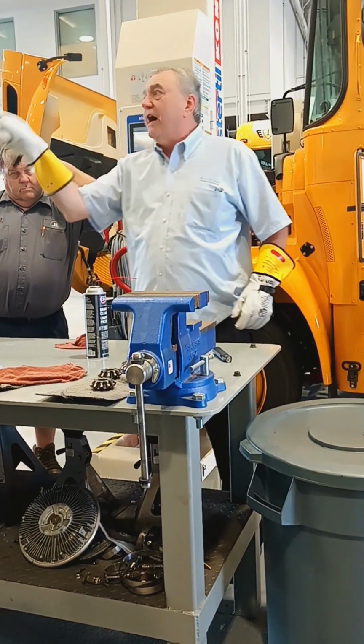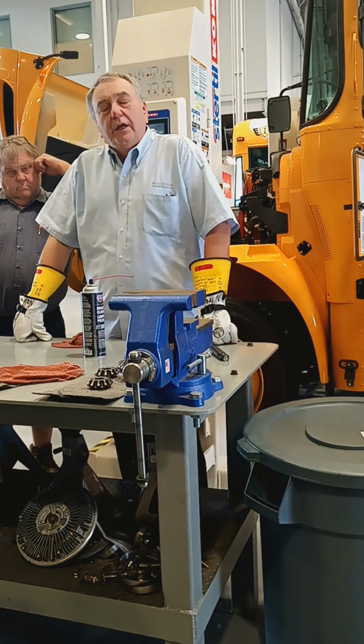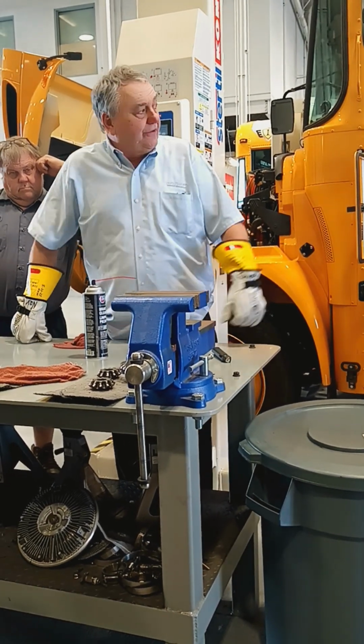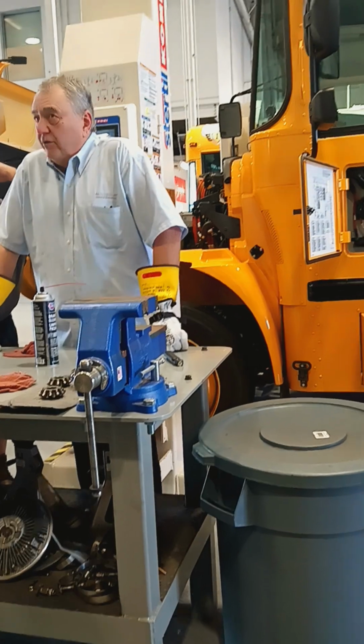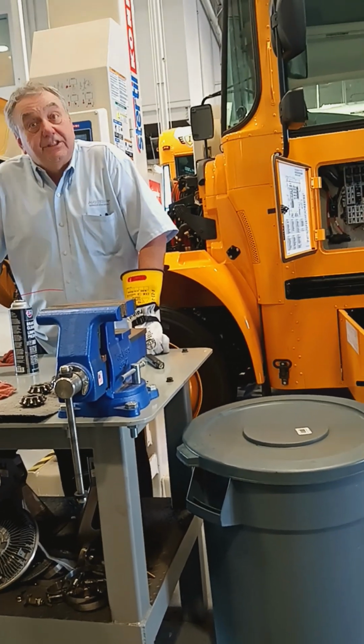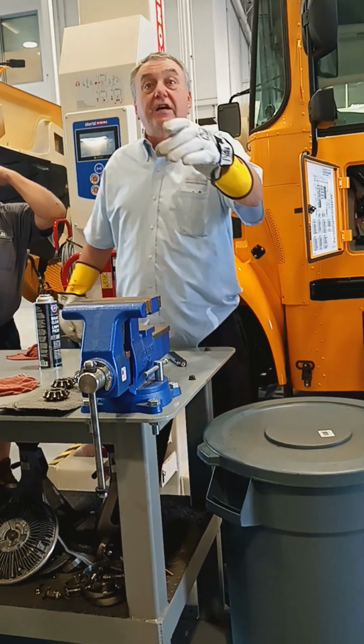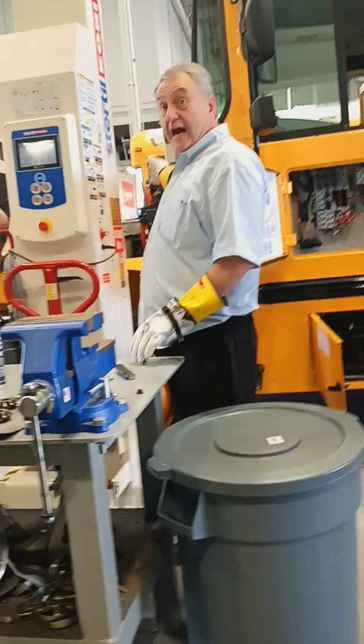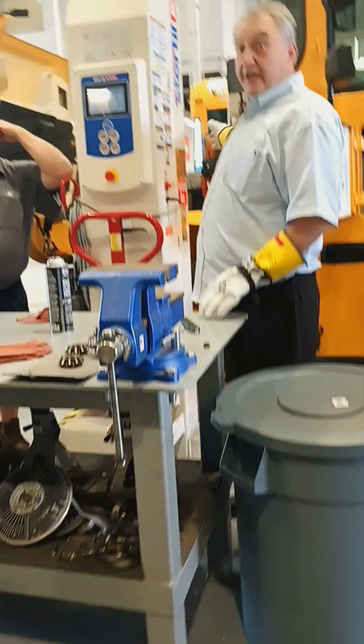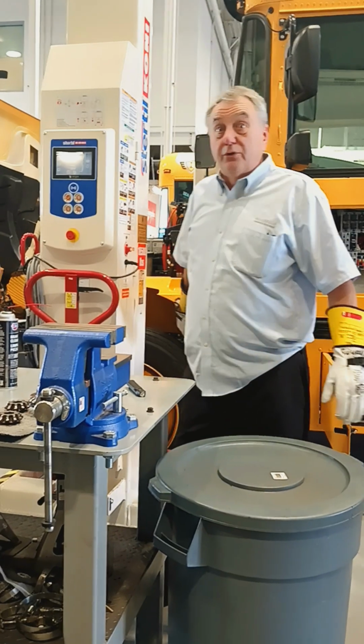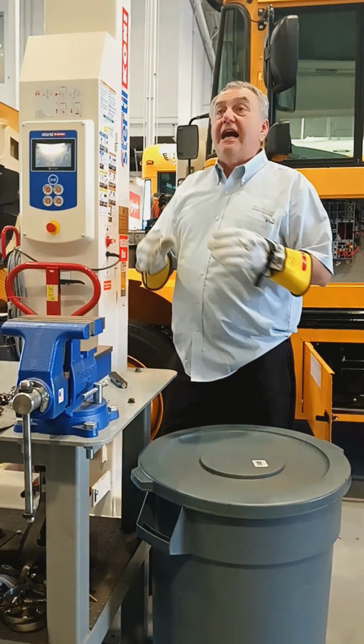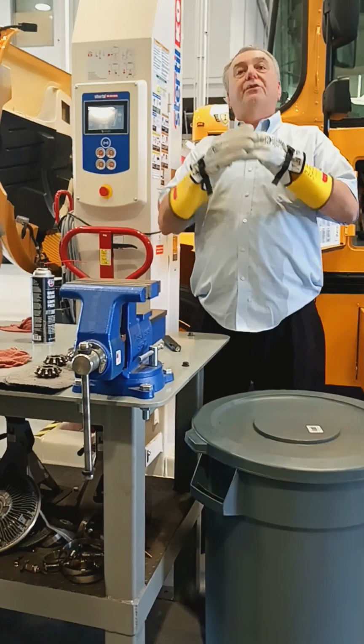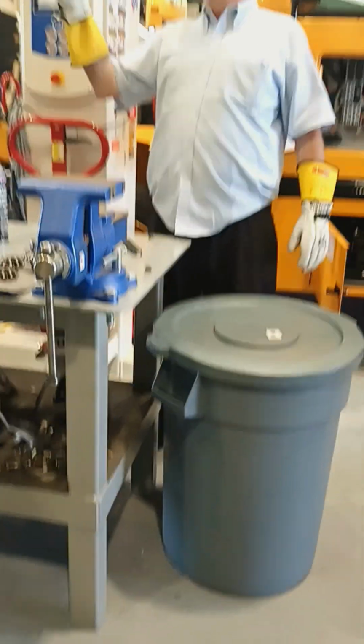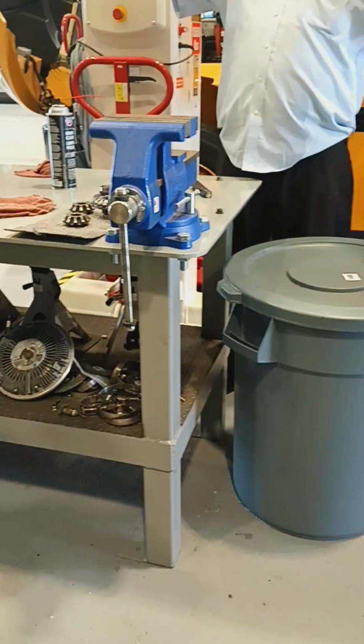That's why you gotta know where the snake is in the cage. If a contactor welds together, this thing will have a shit fit. That's in the S-box, yes, but there's other contactors also in the high voltage distribution module. You don't know when something's gonna weld together. That's why we're saying you have to know where the snake is in the cage. You gotta follow the process, not assume you don't need to disable this time.